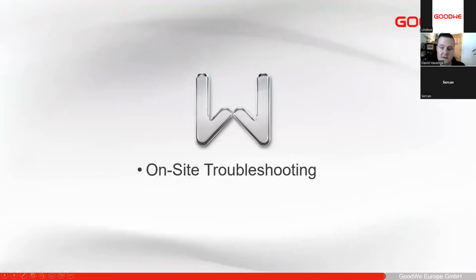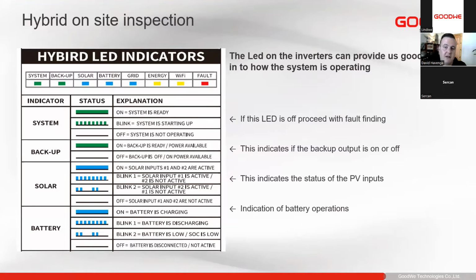So next we have the on-site troubleshooting. So on all of our inverters, we have LEDs that give us a lot of indication. I won't go into too much detail here because each different model of inverter has a slightly different variation of the LEDs. Also, the newer ones also have different LEDs. It's important to make sure this guide, as you see here, is always in the user manual for your device, as well as printed on the left-hand side of the inverter as well. So you can always reference that to see what is my inverter indicating.